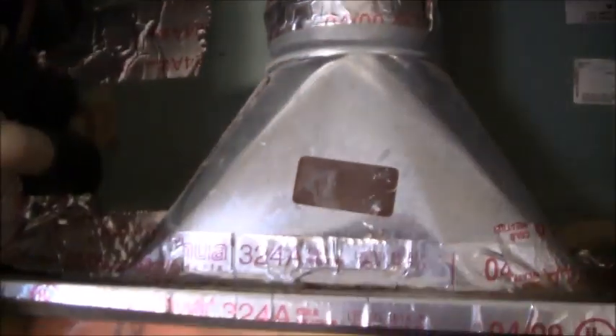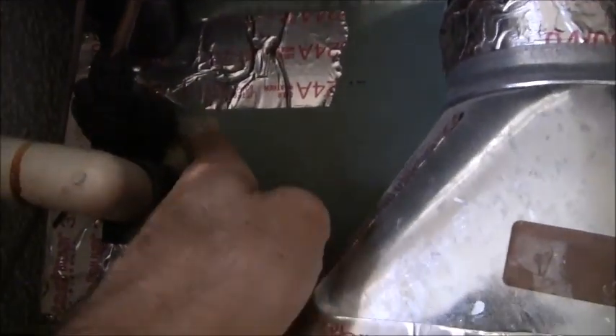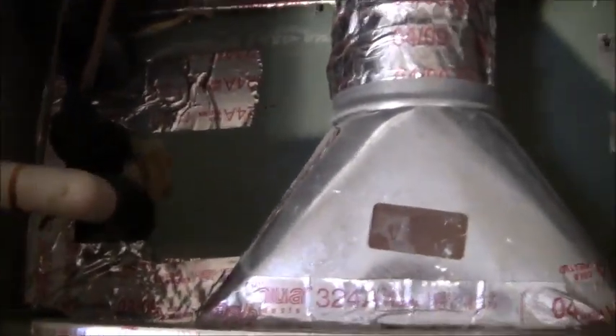It's terrible design. The new systems, you can take a panel door off to gain access to the coil. This system is so old you cannot gain access to the coil. So I'm just going to make an assumption that this is a fixed metering device. What that means is that we're going to use the superheat method when we get to this stage of the system checking to determine if the charge is correct. We're going to use superheat for that purpose because of the metering device of this device here.